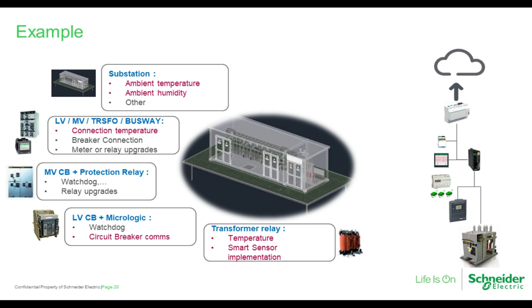With low voltage, again, with some of the new trip units that are out there, we can also add additional protective devices other than just long time, short time, instantaneous, and ground. We can do phase loss. We can do differential now with some of the added on digital modules that can be provided with new breakers and new low voltage equipment.